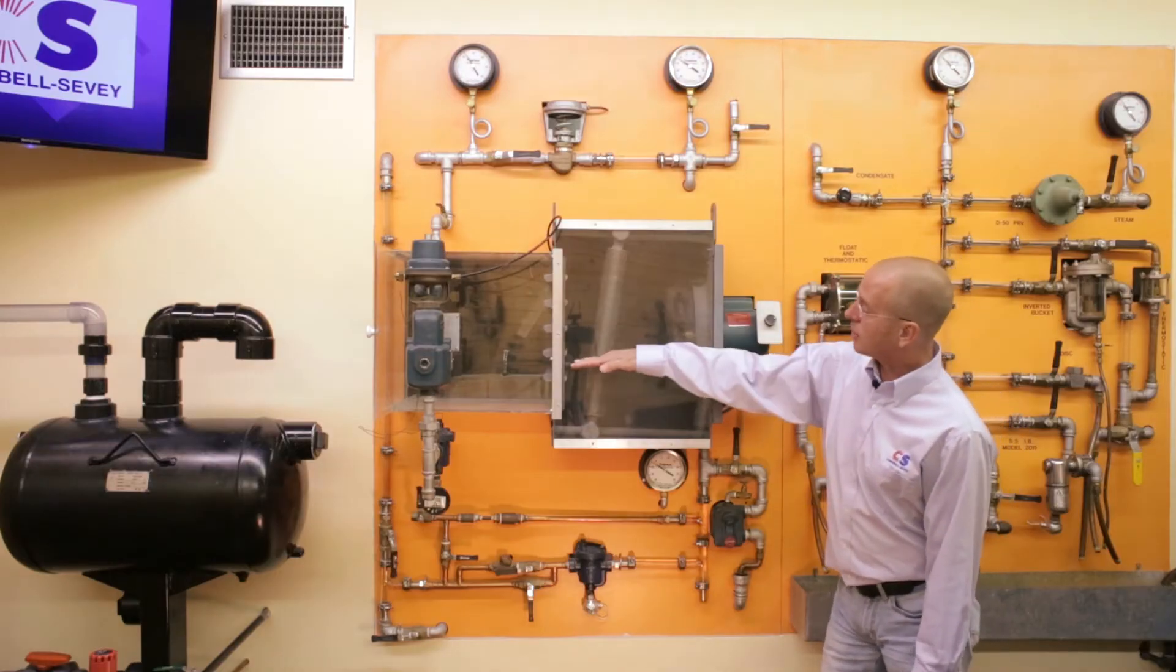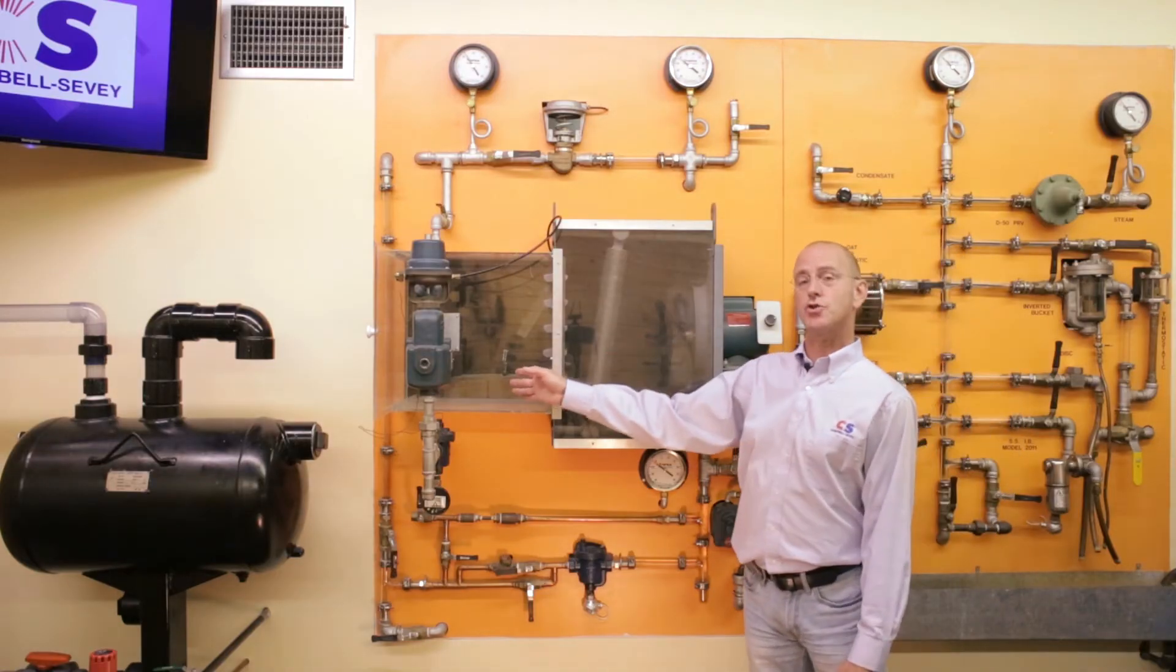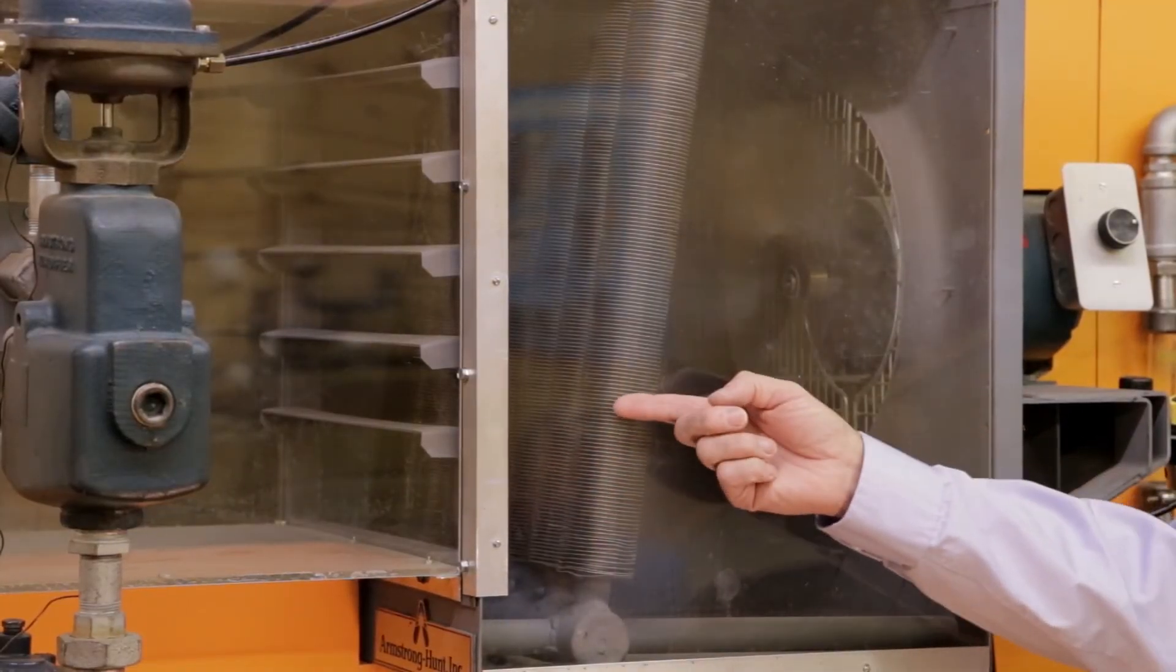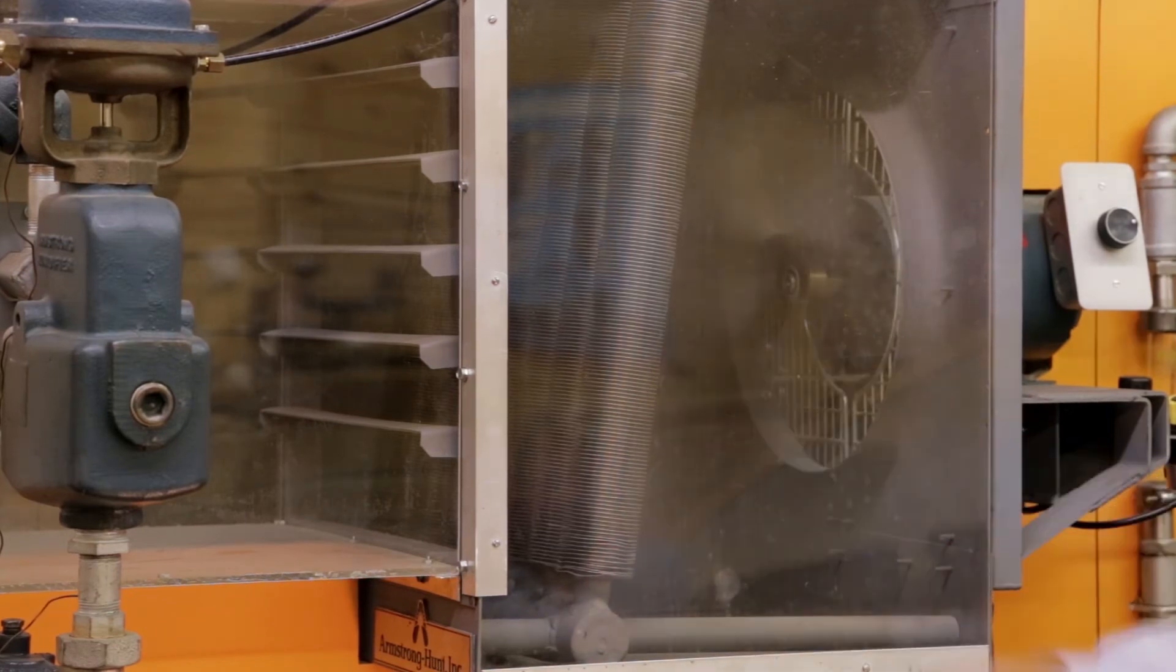If we've got condensate laying in our coil, that either leads to temperature control issues downstream, or we can have water hammer, or we can have the potential for freezing, or long term we'll corrode our coil.